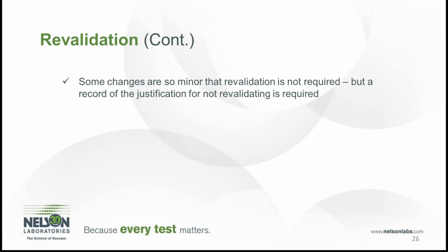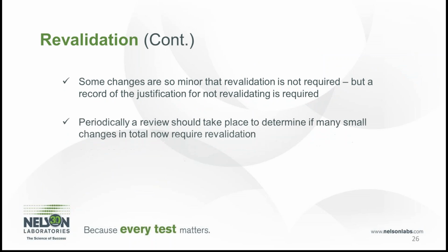It is important to note that some minor changes may not require a revalidation, but it needs to be documented and justified that the revalidation is not required. Also, you should look periodically at your minor changes, because one or two minor changes may not require a revalidation, but 5 or 6 minor changes may qualify as needing a new revalidation.